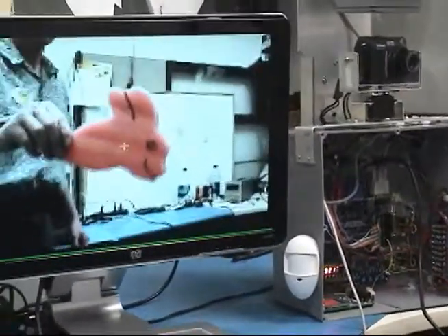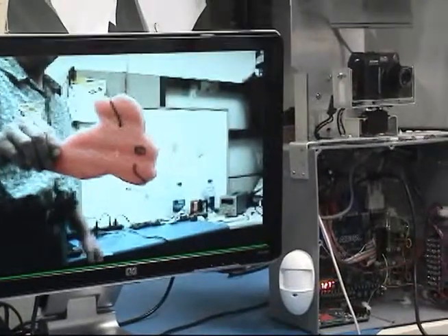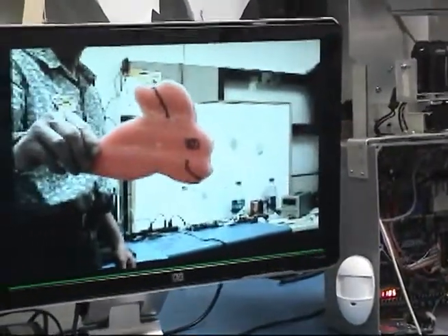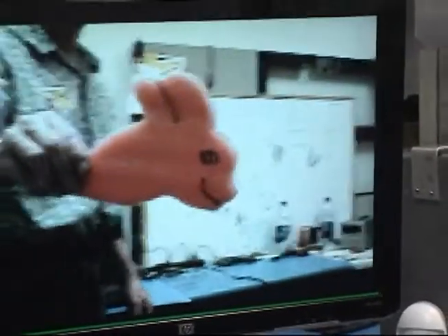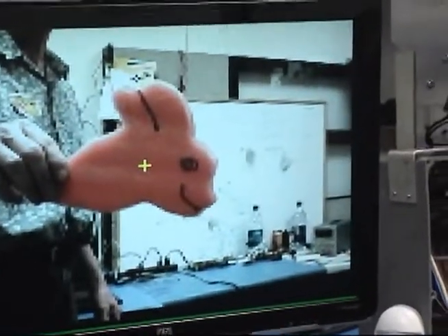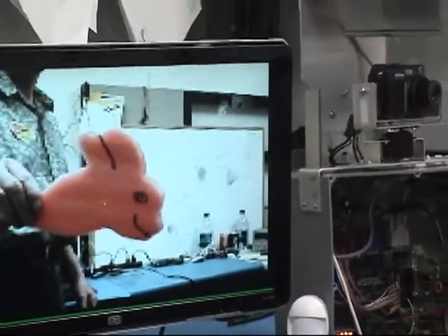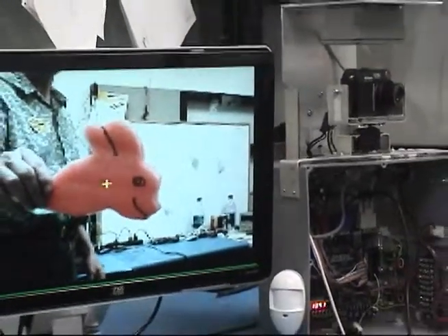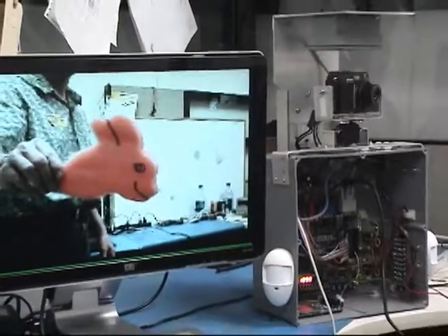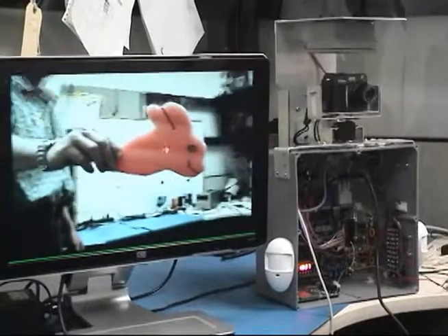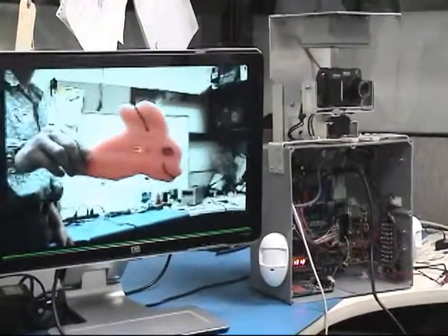across there. So the idea is that the centroid that's calculated and shown in the yellow crosshairs is fed into the servo control system, and the difference between where the crosshairs are and where the center of the field of view is, is the error signal that the control system uses to keep the centroid in the center of the camera's field of view.